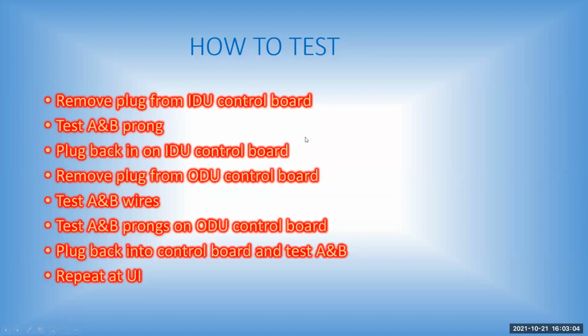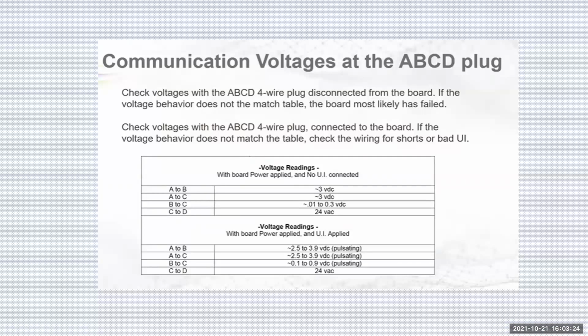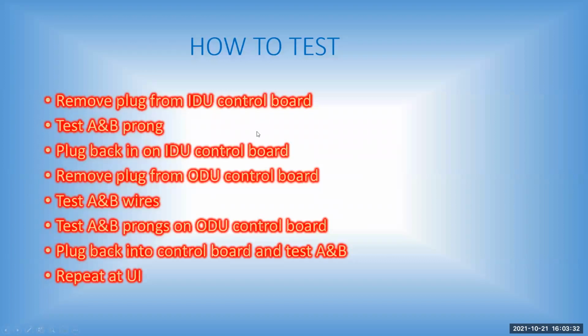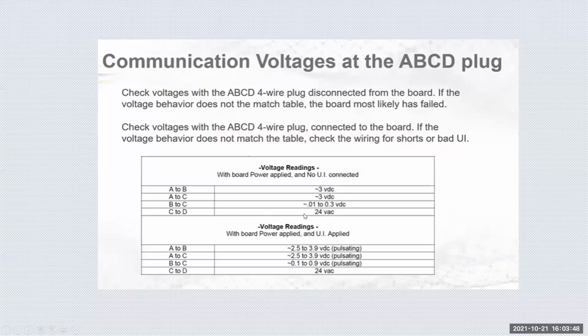On your furnace board, take your ABCD plug off of your furnace board, power applied to your system, check DC voltage between terminals A and B coming straight off the board, right on your pins. If we refer back to that previous screen, you should have roughly 2.5 to 4 volts DC between A and B pins coming off the board. So we'll use 3.5 as a round number in this conversation. So you've got 3.5 coming off your board with your plug disconnected. Let's back up one screen again. Top half of this chart, you're disconnected, bottom half, you're connected. You plug back into your board, now you should be getting 2.5 to 4 pulsating voltage between A and B.